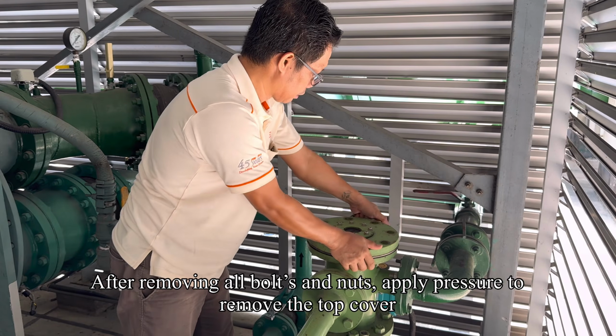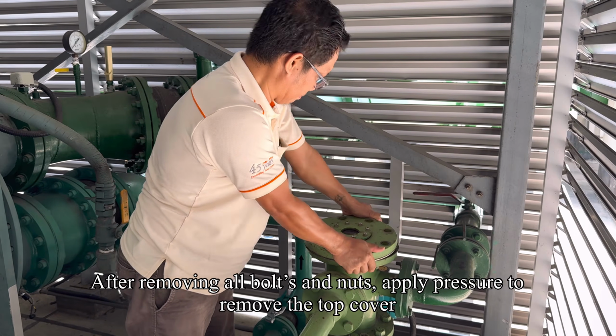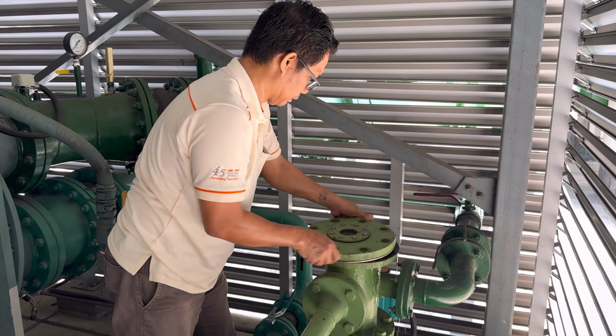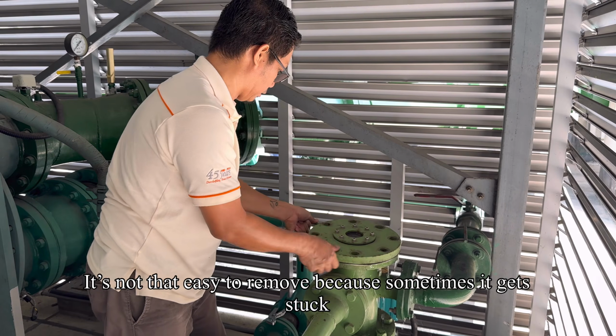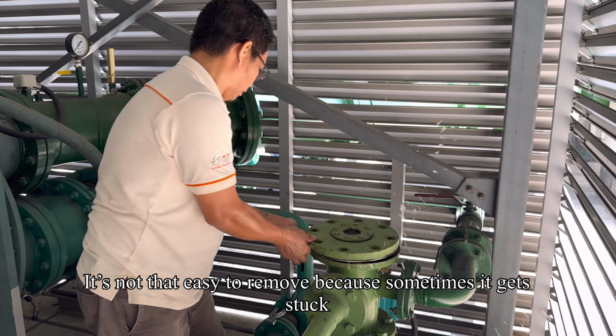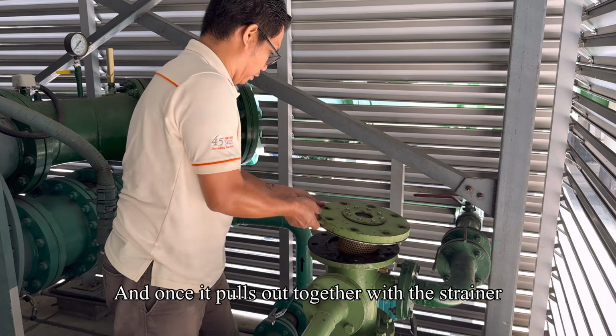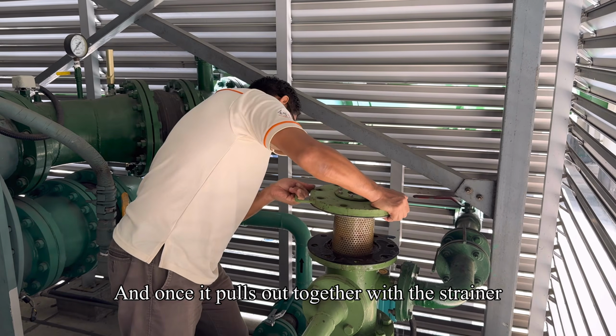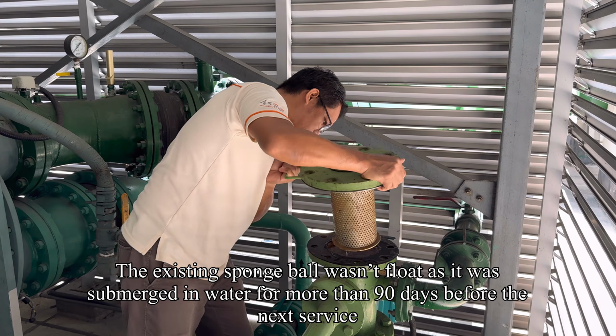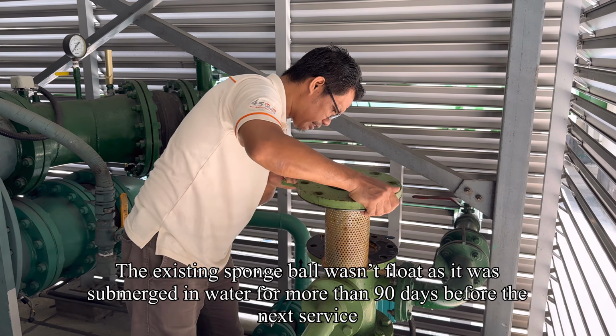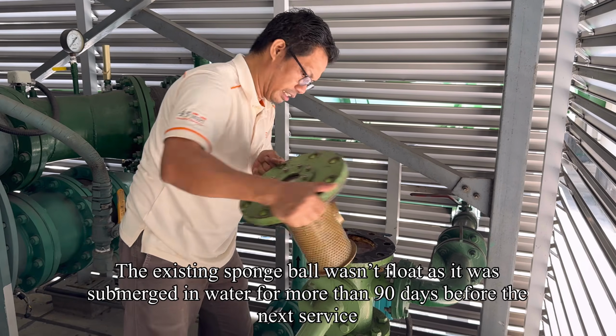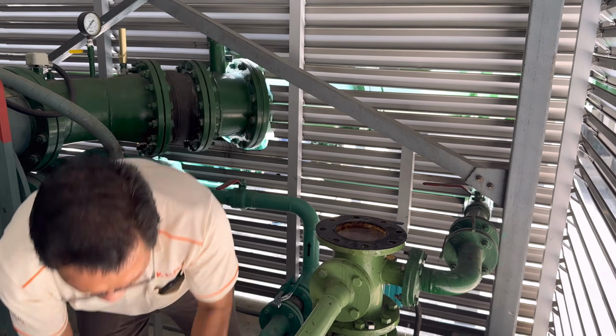After removing all bolts and nuts, apply pressure to remove the top cover. It's not that easy to remove because sometimes it gets stuck. Once it pulls out together with the strainer, the existing sponge ball wasn't afloat, as it was submerged in water for more than 90 days before the next service.